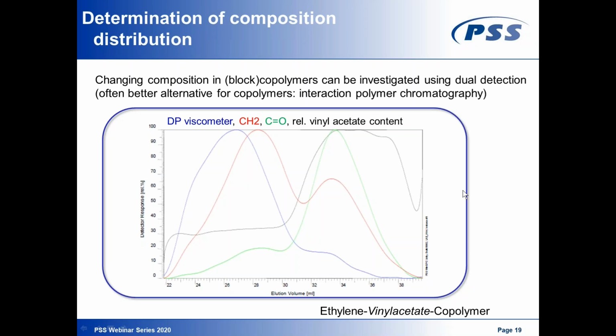This is only part of our high temperature equipment that we do have, and still the problem is that with ambient, the applicability of an IR detector would be very, very limited due to the solvents we need to use there. So the answer is correct that you gave. It's unfortunately no, only for high temperature GPC.